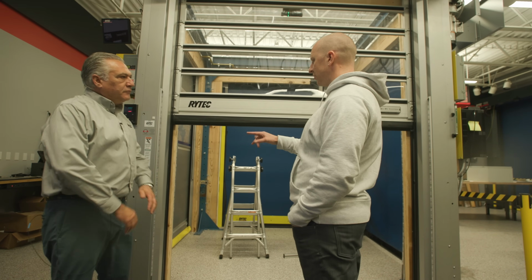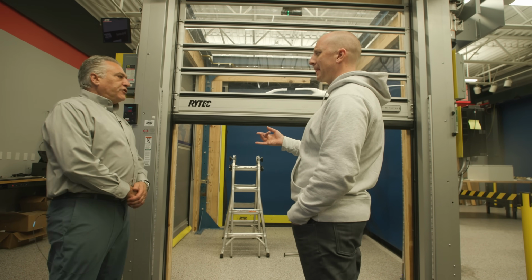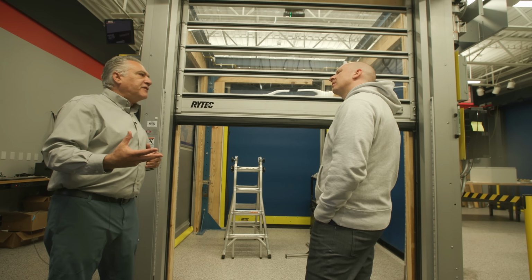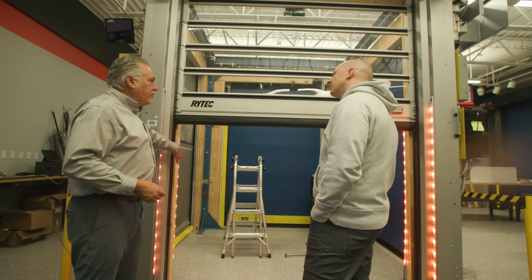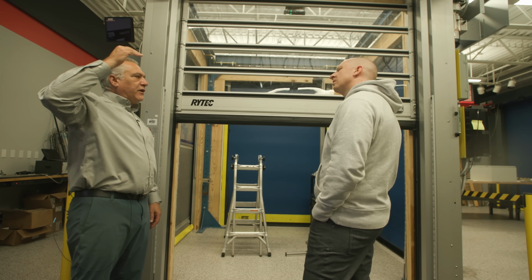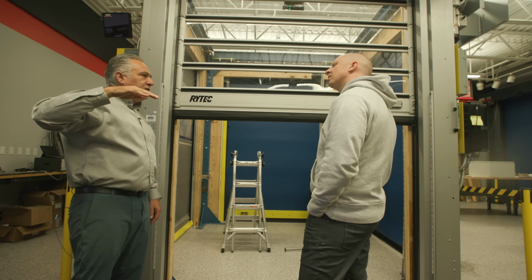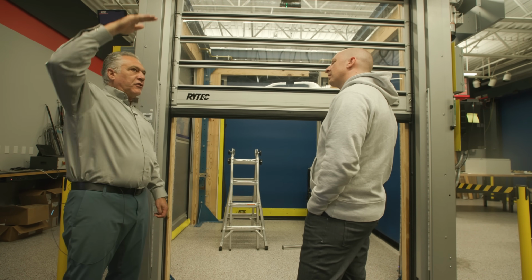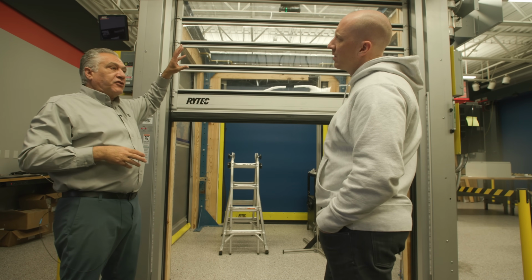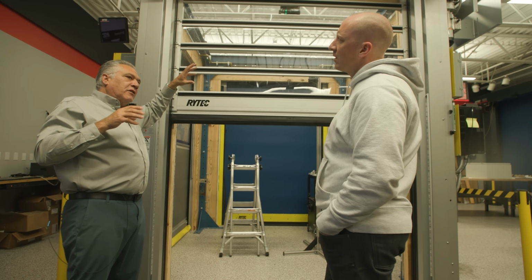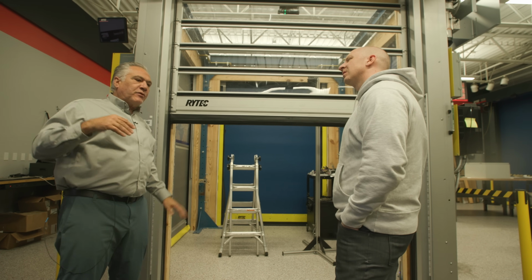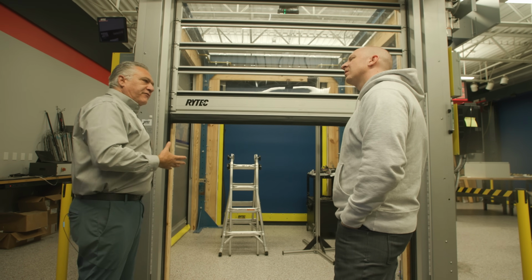So are the two light curtains redundant then? This one is really, the Smart Surround system, it takes things a step further. The light curtain in the door line, what makes it intelligent is its ability to track through software, so that when a beam is blocked, it knows it's the door. As it blocks each individual beam, it's looking at the encoder positioning system to say, where is the door? That's why the beam's being blocked. That's what's intelligent about that part, and that's our last line of defense, if you will.